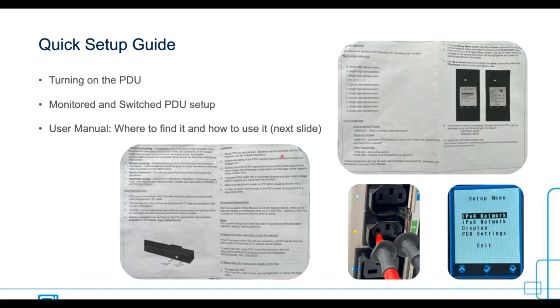Next, you will test the unit with a multimeter to ensure proper outlet voltage before plugging in any equipment. The PDU power should be off before plugging in any equipment, and once it is plugged in, turn on the equipment in a sequential order to avoid a current surge to the PDU.